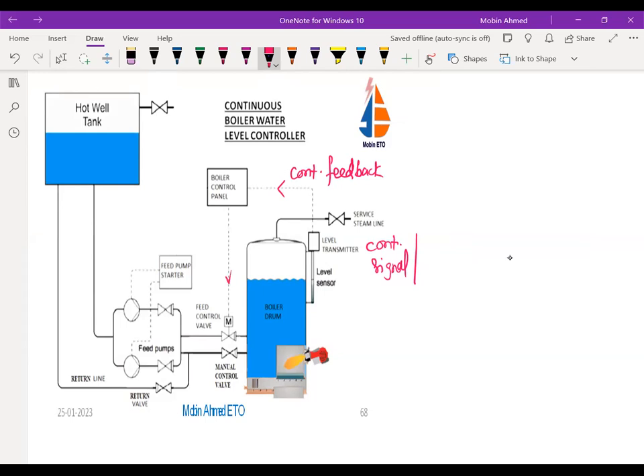Okay, then this is going to the control output. So here we are going to use PID control or PLC control. So we are going to have a continuous control output, which is going to vary the feed control valve. Now these pumps are running continuously. One pump is running and one is standby. One feed pump continues to run, and the valve is adjusted continuously as per the required level. So the flow of the water is being controlled.